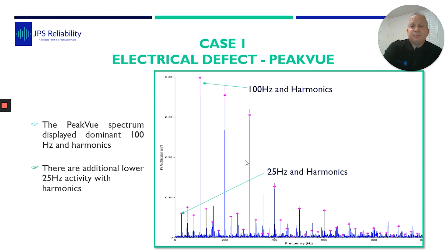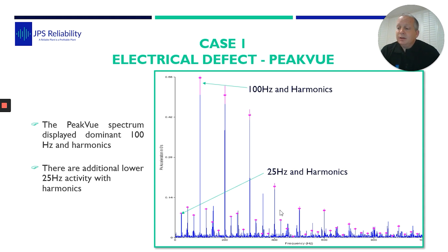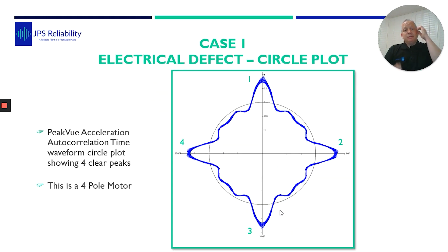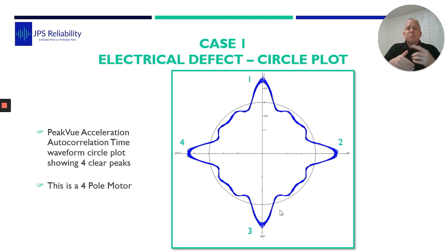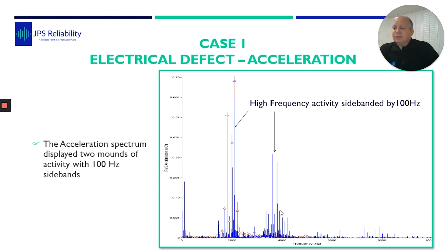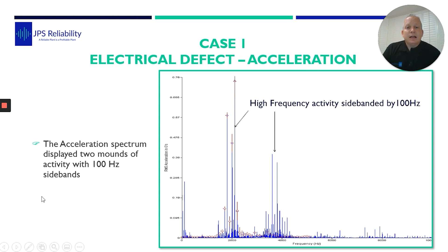But this was the change in the pattern. In the velocity spectrum, we can see what wasn't there before — a 100 hertz component. And in the PeakVue data we have lots of 100 hertz series and also 25 hertz harmonics. To look at the data differently, we put in a circular plot. We ensured the RPM was spot on — 100%. The circular plot showed there are four pulses per rotation of the shaft. Coincidentally, it's a four-pole motor. This is the acceleration data, where we have two mounds of activity side-banded by 100 hertz.